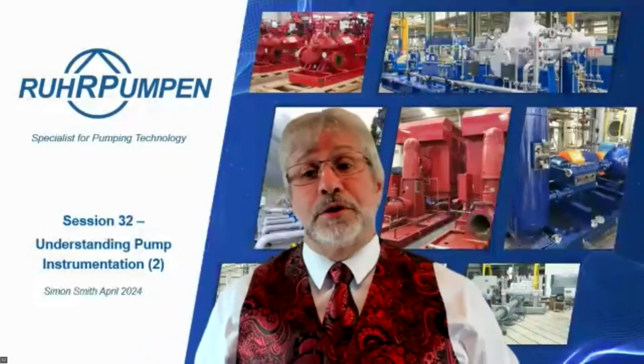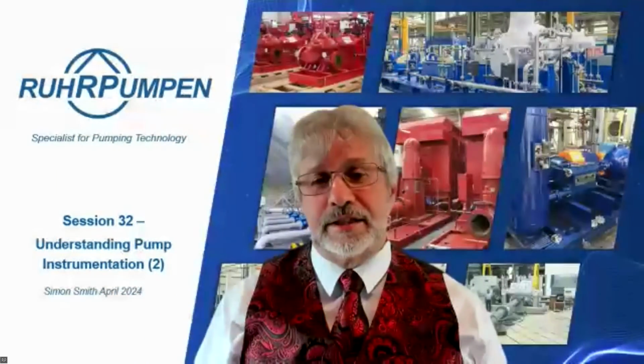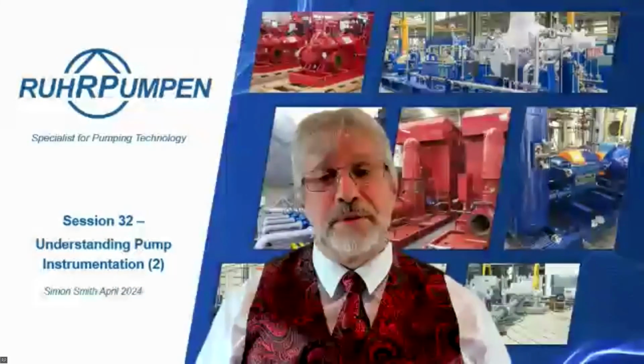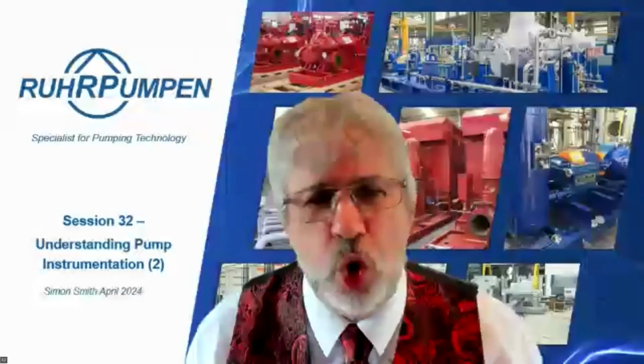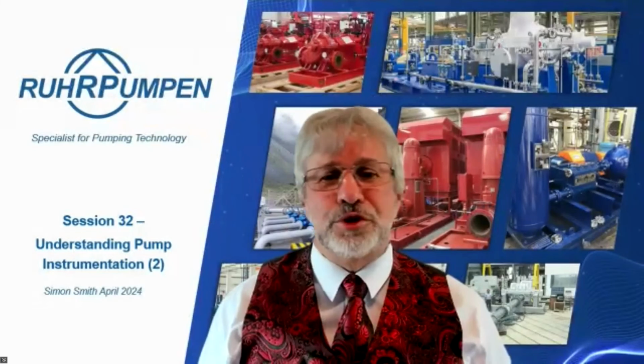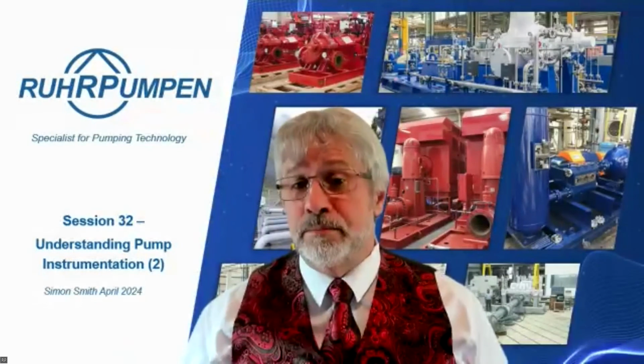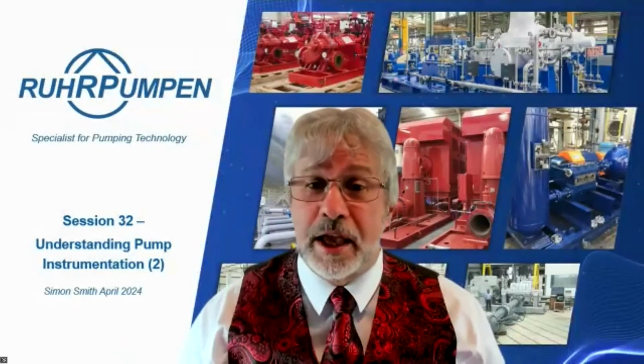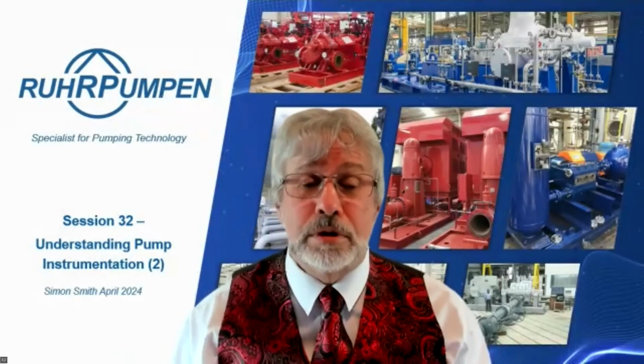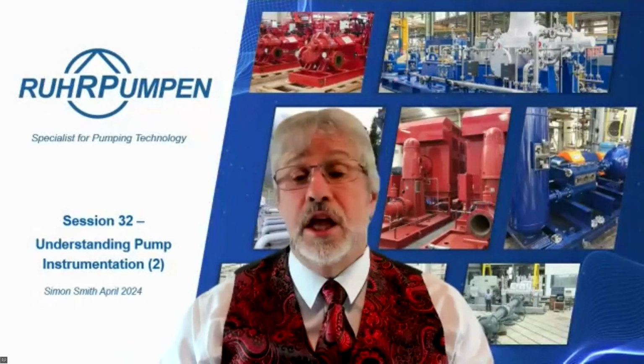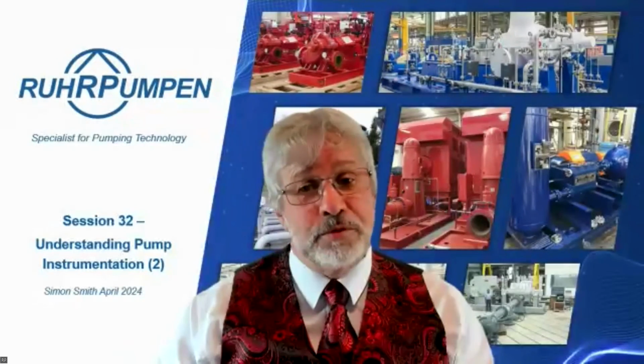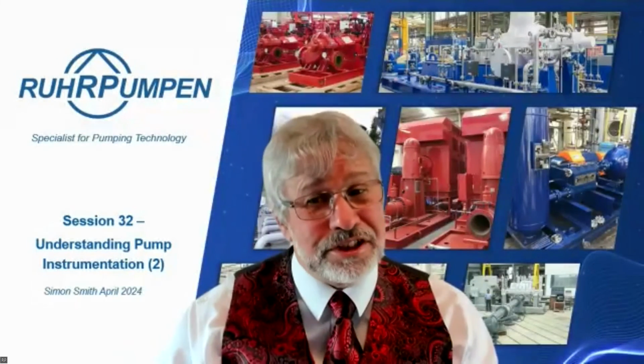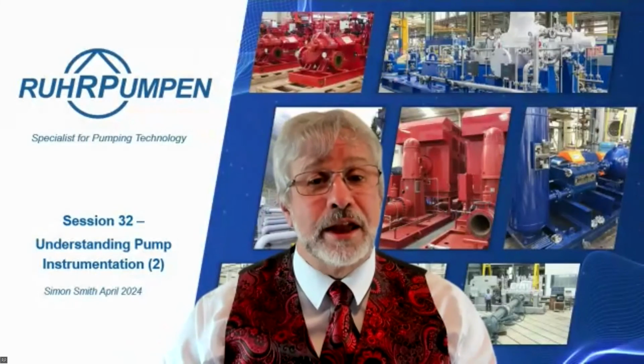Yes, we absolutely do it, especially on more complicated, larger, high-speed pumps in particular. An OH2 pump doesn't normally need lateral and torsional analysis, but a high-speed axially split case pump or barrel pump, yeah, we will normally have to do these calculations. Vertical pumps, torsional vibration analysis, natural resonant frequency analysis, very important. So yes, we do regularly do those on more complex pumping systems.